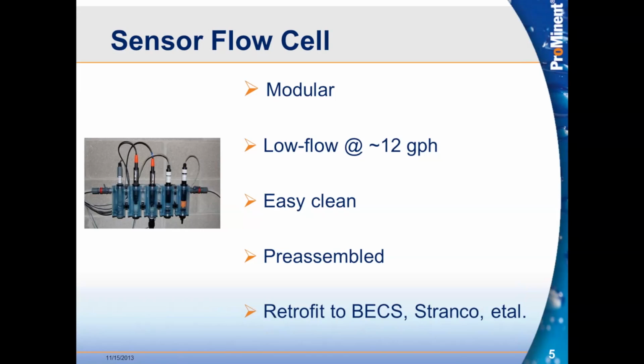The other side of this too is that the sensor flow cell is pre-assembled. With the controller, it comes pre-assembled on a backboard, and you don't get a bag of parts that you have to assemble. You don't have to tape each fitting up and then assemble it on site. Our systems come pre-assembled, pre-wired, ready to hang. So I think that's a big plus for people who are looking for ease of installation. And again, the flow cell along with the sensors, although it's not an optimal situation, can be retrofitted back to certain Bex and Strantrol units.